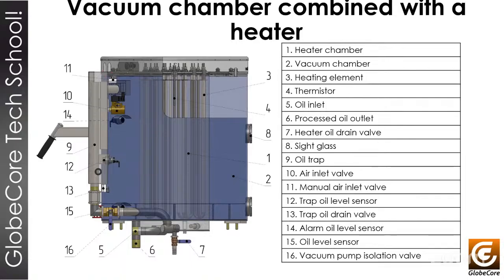Also, we have here in gray color the oil trap, because if the oil level in the external chamber increases a lot, and the oil reaches this point, the oil can move from the vacuum chamber to the vacuum line, and we do not want this. We will find a sensor set here, and when the oil in the vacuum line reaches this level, the machine will stop the process. That will help us prevent possible mixing of oil between the vacuum machine oil and the oil you are working on for the cleaning, and that will be really good for the procedure.